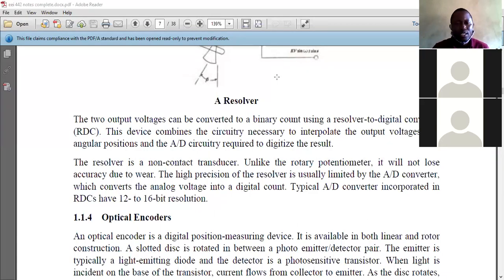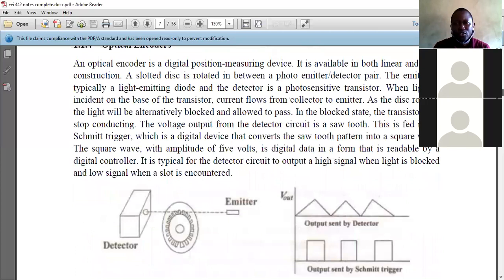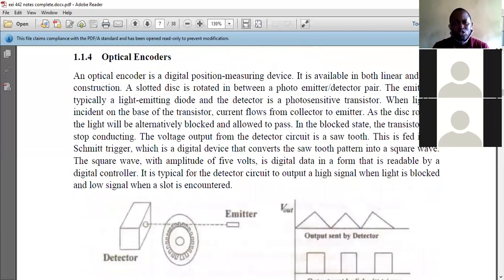There is something similar between encoders and resolvers. The similarity is that both of them can produce digital results. Analog to digital converter is applied in a resolver. Now, an optical encoder can also give us a digital output. It's a digital position measuring device, available in both linear and rotary construction.